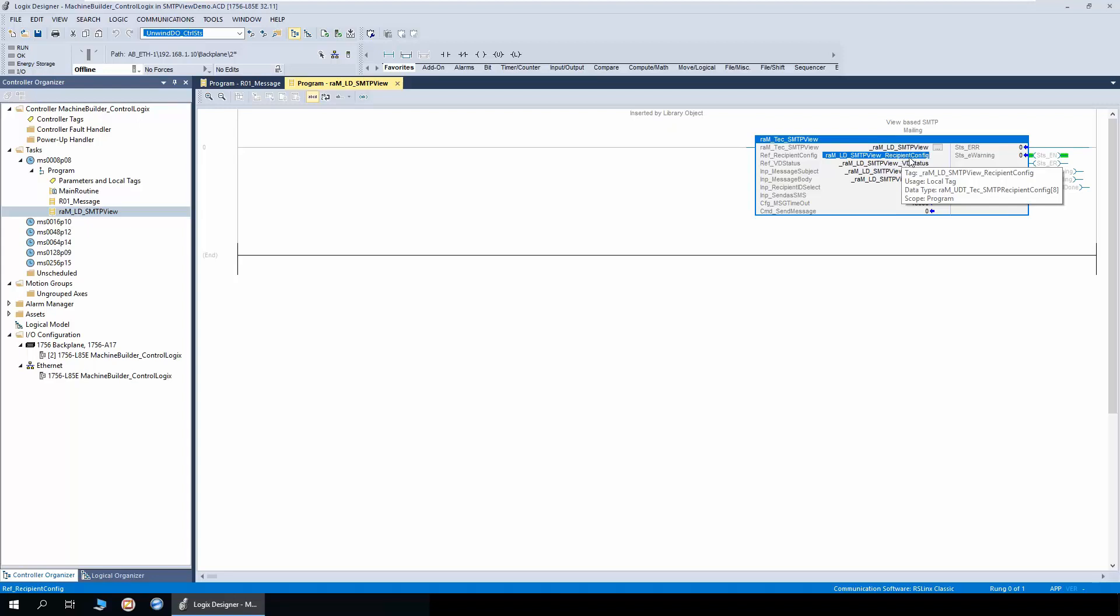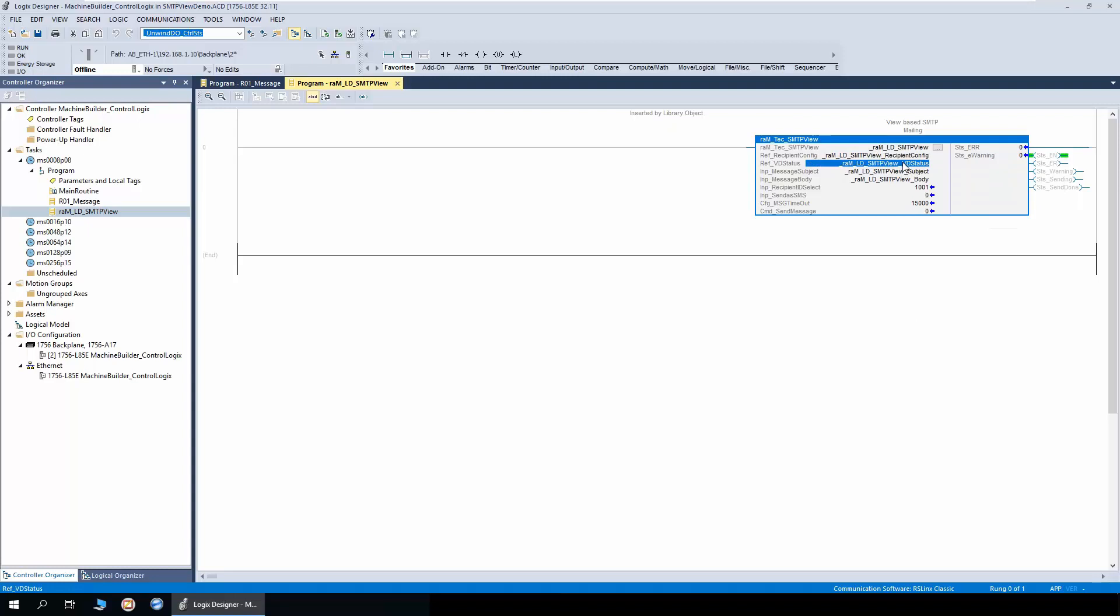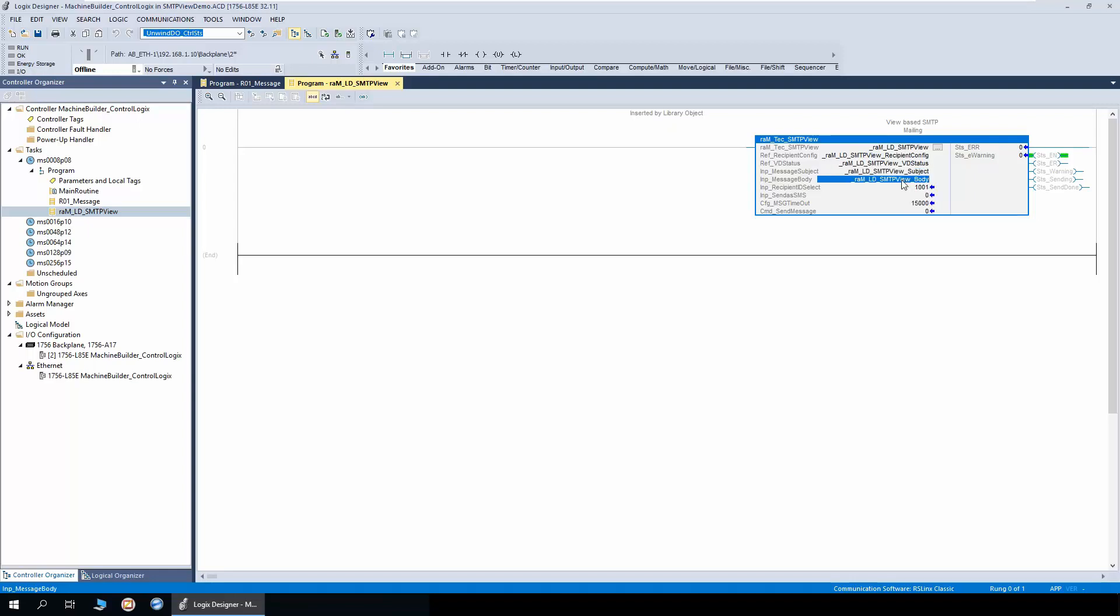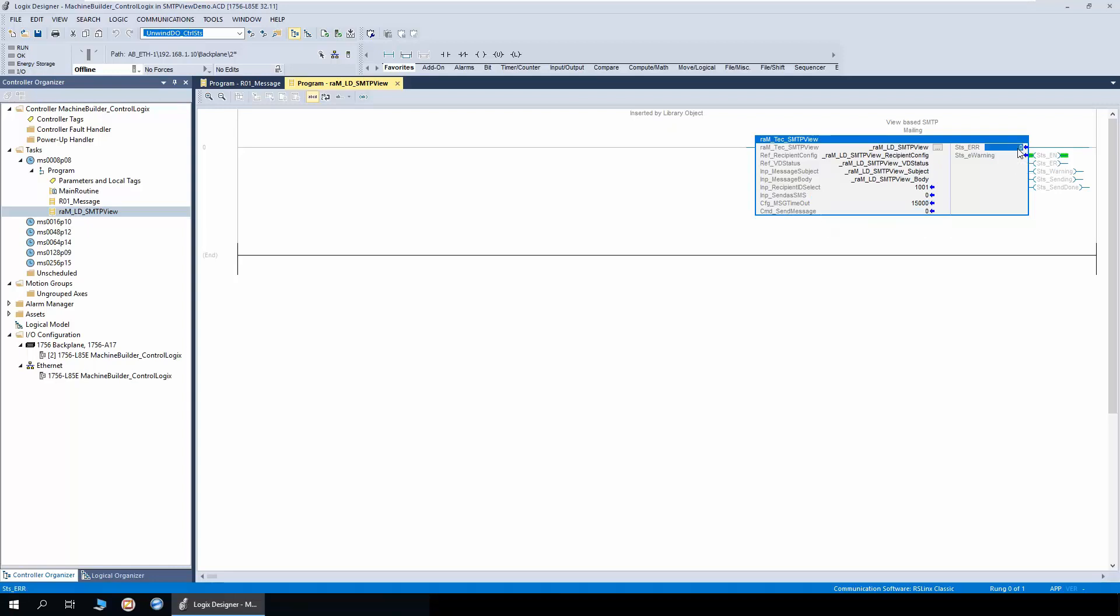So depending on the number of recipients you want to have in the application, you can size the array. The second is exclusively for the view designer faceplate, which is the VD status. The third is the string tag where the subject of the email is to be moved. This is the body of the email or SMS. Recipient ID to be selected through this tag. This is to select if the content has to be sent to the email ID or the phone number as SMS. Message timeout configuration and lastly the command to send message. There are few status for error and e-warning.